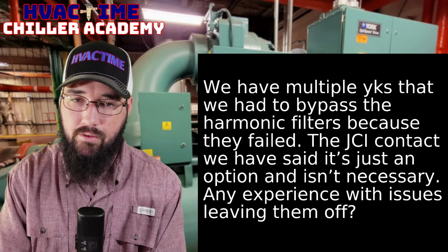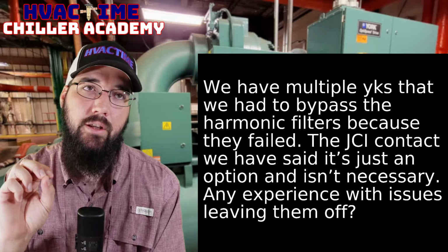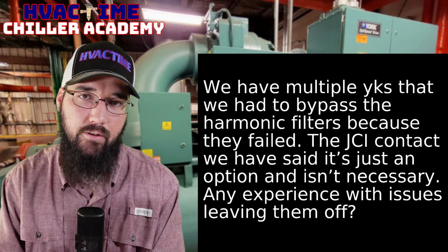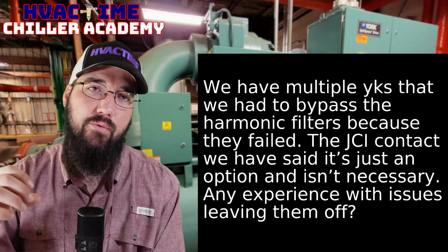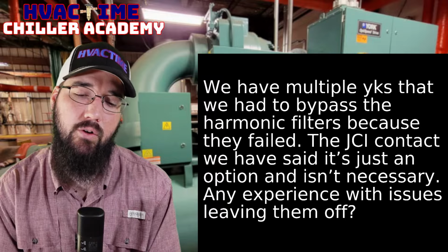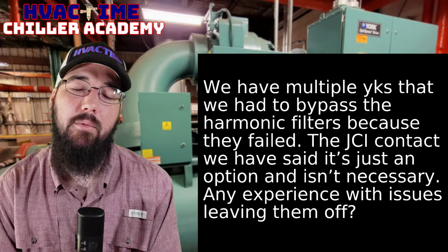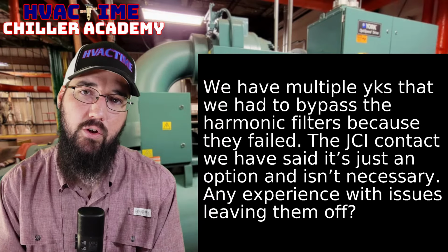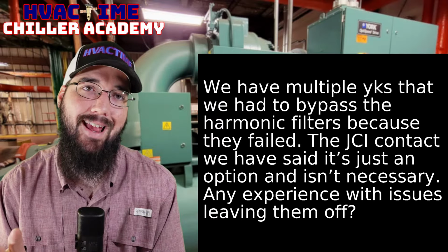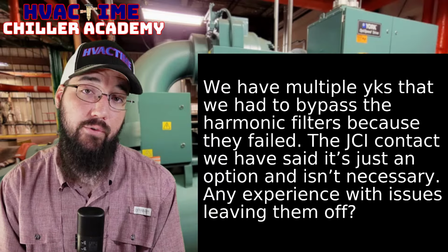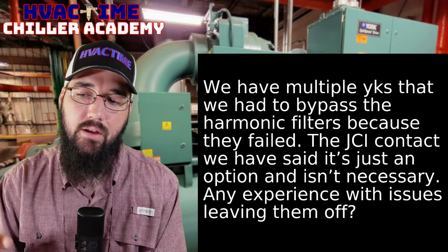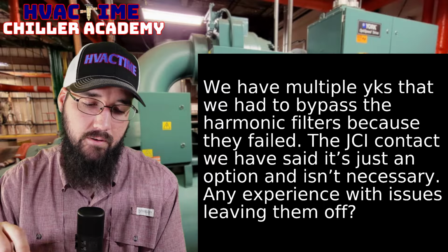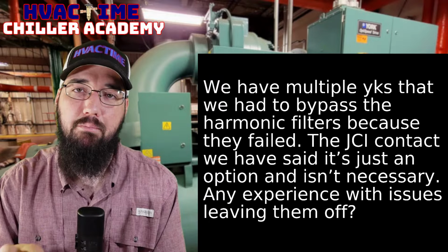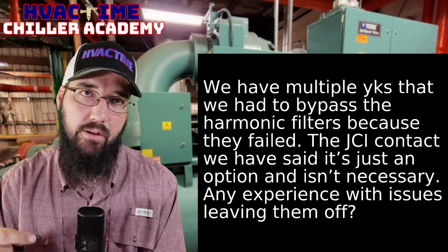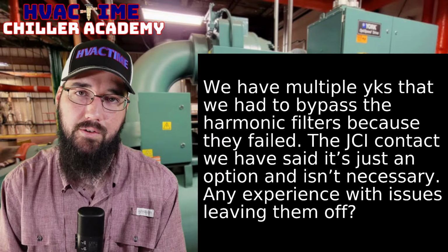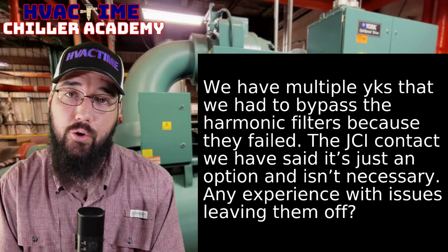This changes now. This goes beyond your YK. Okay, so when you start getting into the YZ and YMC squared models, we have the next generation of drives in those, and those are a lot more advanced. The newest ones, from my understanding, have a harmonic filter assembly that's different, and it's a built-in feature. So on the newer drive assemblies, it's not an optional thing. It is part of the core assembly. I don't know on those new ones if you could even bypass it if you wanted to.